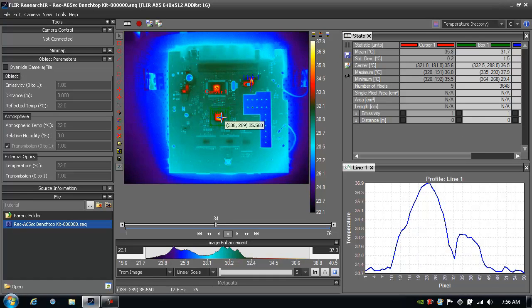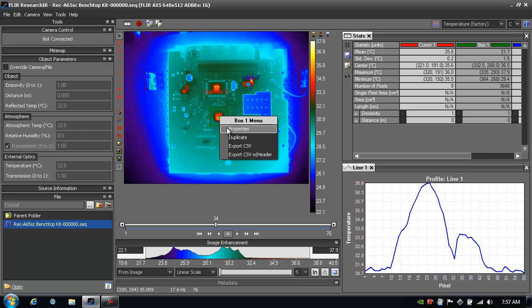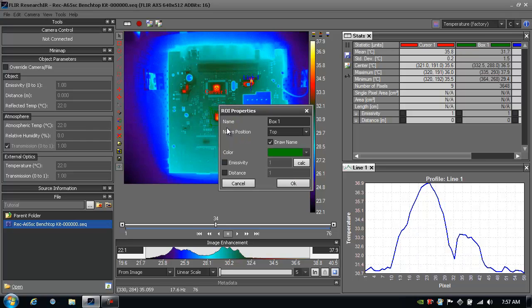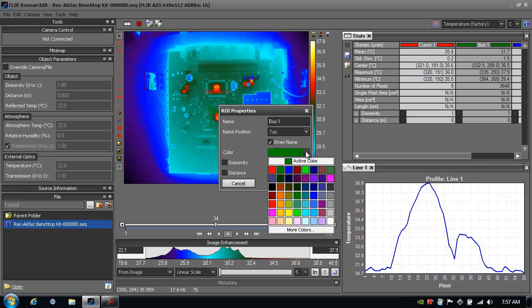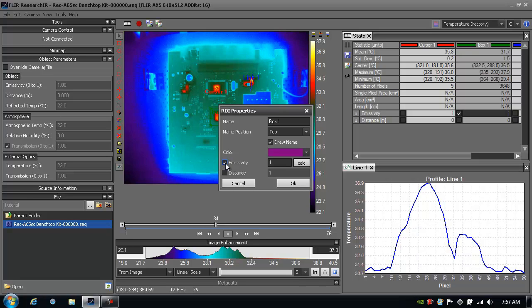And now let's go ahead and click on the box here. It's green, so it kind of blends in there. If I right click, I can go in and change the properties of it. So let's say we want to change the properties and give it a different color. Maybe I'll make it a purple. And I could give it a unique name as well. This is a good part, too, to also show you can create local emissivities. So one of the things about IR is you won't always have the correct emissivity entered. And if I happen to have a board like this with different objects with different emissivities, I can create a local emissivity just by clicking on the emissivity and typing in a new value.